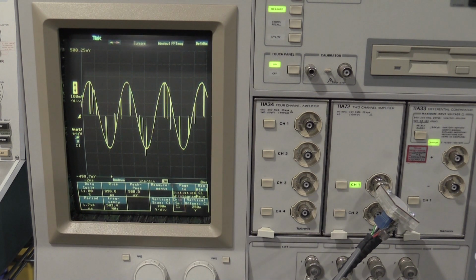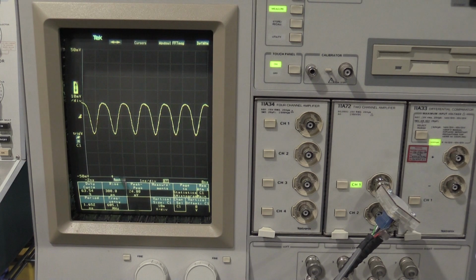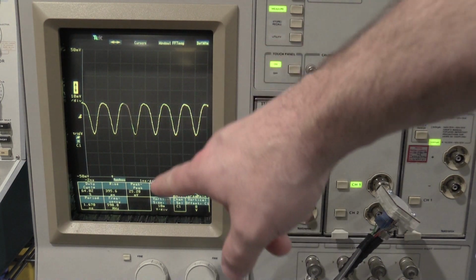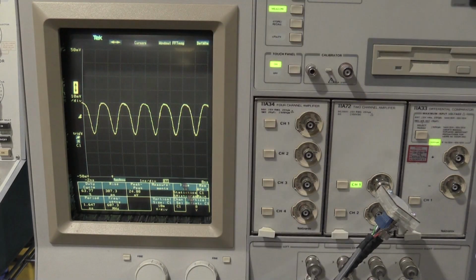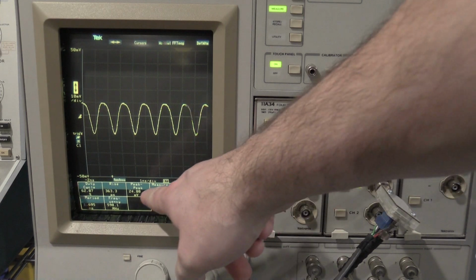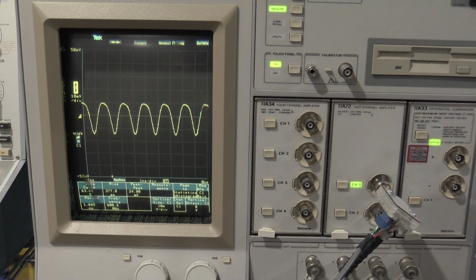This should read about 600. It's building something. And here we are in the high mode. So you'll notice a drastic change in the vertical sensitivity. I had to go down to 10 millivolts per division. We're at 24 millivolts peak to peak as opposed to 500 millivolts peak to peak.